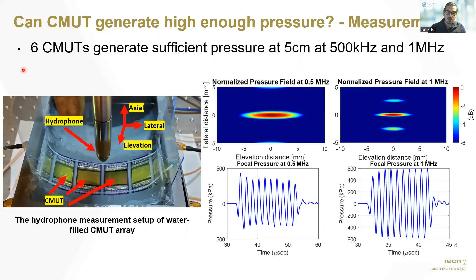The simulated transducer array design was later transferred to 3D CAD software and manufactured with a resin printer. Then CMUT arrays with electronic boards were placed into the printed CMUT housing. The water-filled structure with hydrophone setup is given in the figure left, and the hydrophone measurement results are given in the figure right. The figure top left shows the pressure beam profile at 500 kHz and the figure below shows the pressure time signal, which has good agreement with the simulation studies. Furthermore, the pressure profile at 1 MHz with the same CMUT arrays is demonstrated in the figure top, and the figure bottom right shows the pressure time signal at 1 MHz.